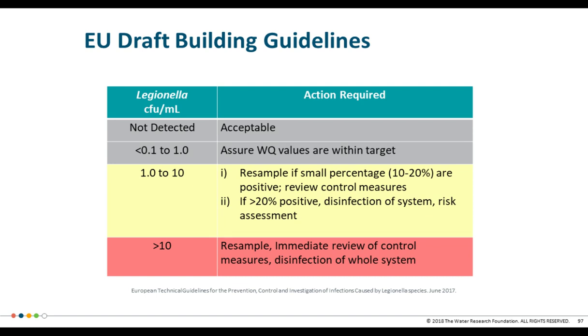But it also shows that if low levels are detected, less than 1 per milliliter, it would encourage the building manager to check their water management plans and look at other water quality values—is there disinfectant, are other control procedures in place? If they're in place and working properly, then occasional low-level detections or concentrations of Legionella may not be unexpected if the system is otherwise operating properly.